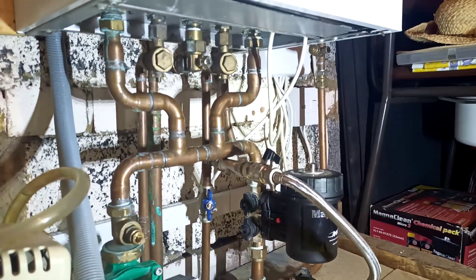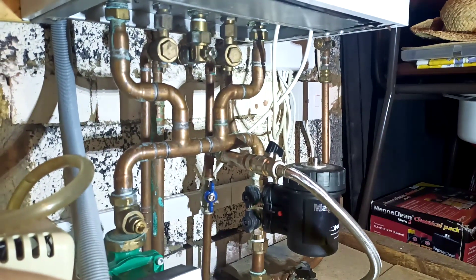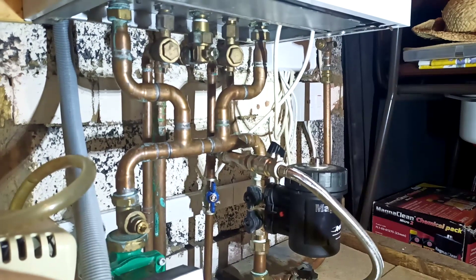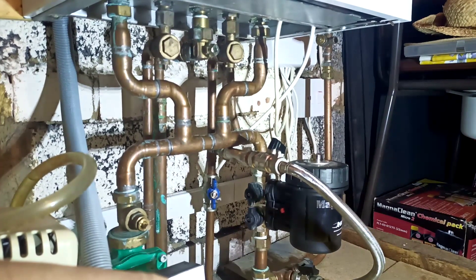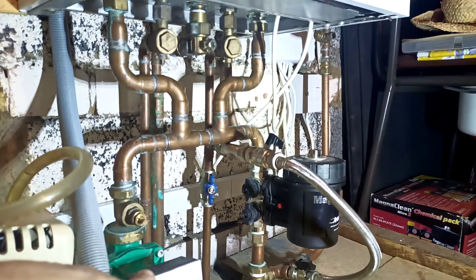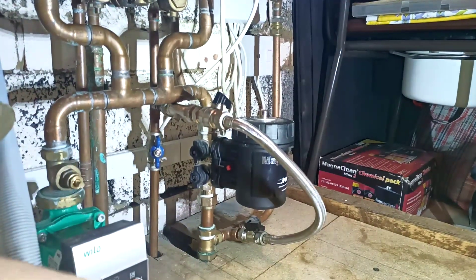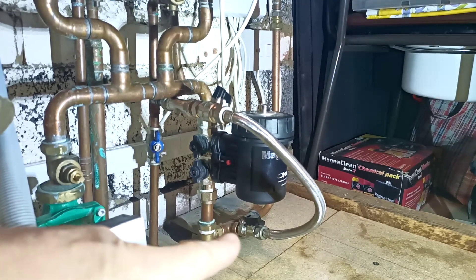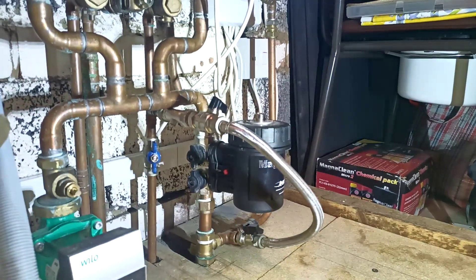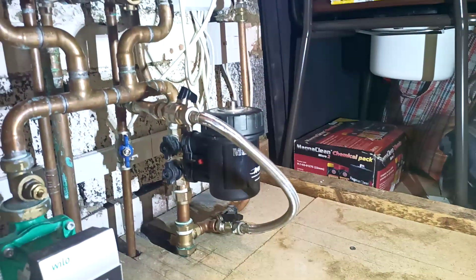I've used these flat-faced unions on the side of the boiler here rather than the Wiesmann valves, and we've managed to fit a pump in. The customer actually fitted this MagnaClean — I didn't fit this filling loop back down there. So this is a traditional additional expansion vessel and filling loop.